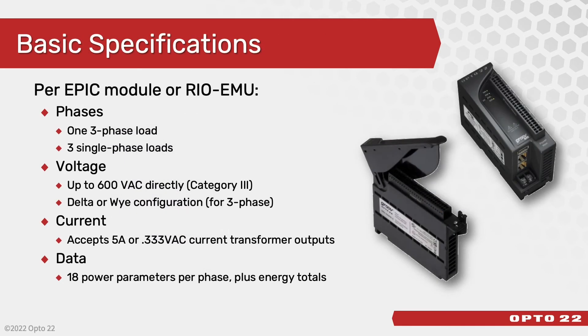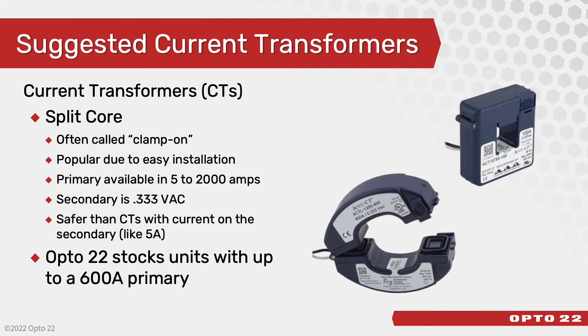Both are designed to connect to three-phase loads. The voltage connection can be up to 600 volts directly, and they can handle either a delta or a Y configuration. For the current connection, they accept either 5 amp or 0.333 VAC current transformer outputs. There are 18 parameters per phase plus energy totals. We recommend split-core current transformers because they can clamp around the feeder wires without having to disconnect them, and are thus easy to install.